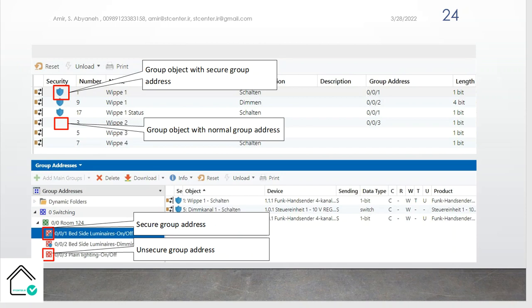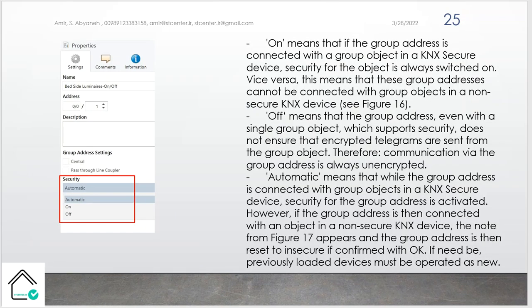Also, when you use KNX Secure devices, the object that you use is secure, and when you add it to a group address, it makes the group address secure. Of course, to have secure communication in a group address, both sides should be secure. Remember that both sides should be secure. Because of that, when you click on the device, this window comes up from the properties settings, and for security there are three options: automatic, on and off. We want to go through it and learn more about it. If you click on a group address, this window comes up, so you can choose on, off or automatic.